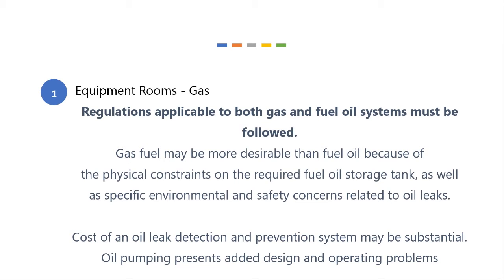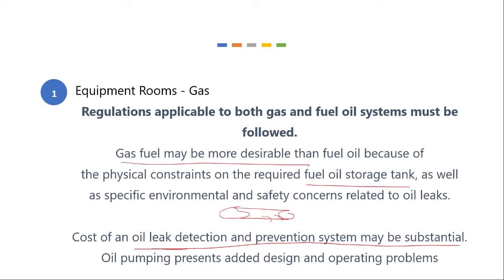So if you're using gas, you must follow the applicable regulations in your jurisdiction. Gas fuel is more desirable because you don't have to store it. What that means is natural gas comes in through a pipeline. Most big cities have a natural gas infrastructure. So since you're not storing the gas, you don't need to have a big tank. Whereas if you have an oil tank that's sitting outside, you have to burn oil and somebody has to come by and fill up the tank every week or however often you fill it up. And there's always a risk that the tank will leak. So you have to consider if the tank leaks, how much will it cost to clean up? And even if the tank doesn't leak, how much will it cost to monitor and detect the leaks?